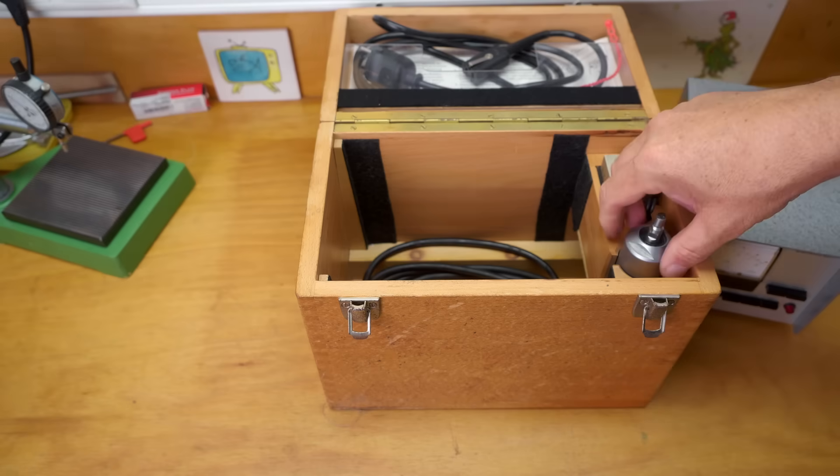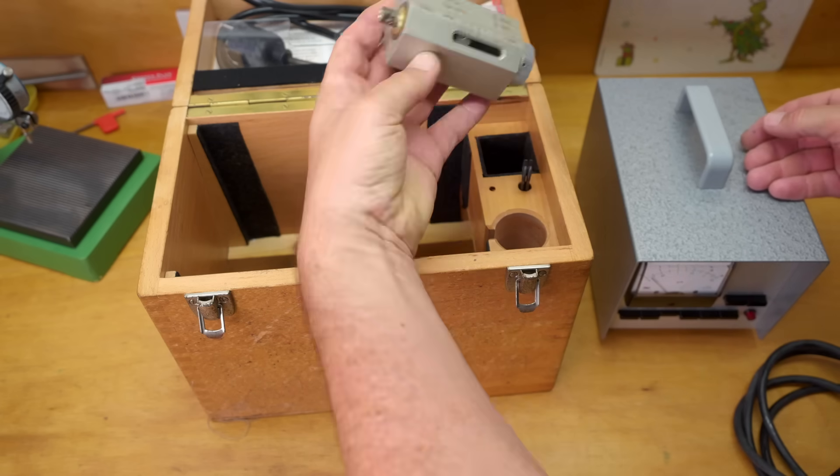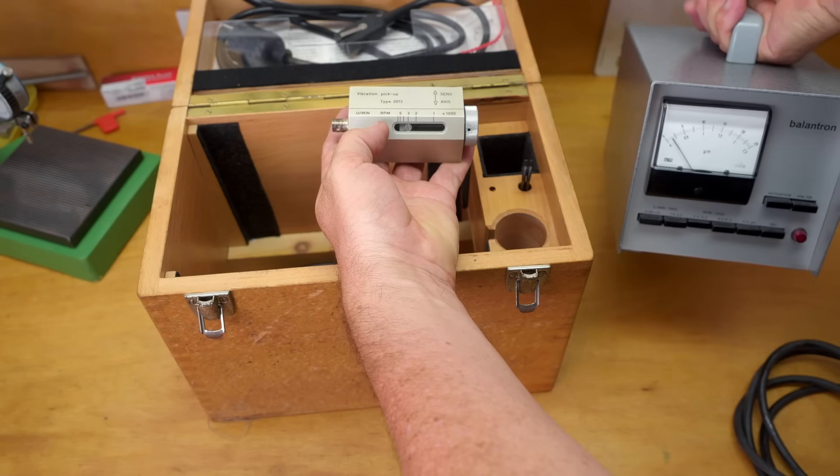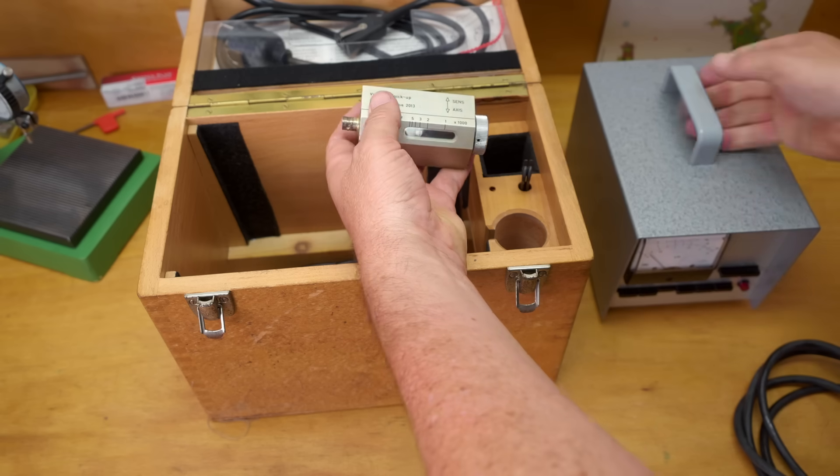The problem with this unit is that this actuator, or as Stefan Gotteswinter put it, handheld highly precise jackhammer, is not working. It's not doing anything. The rest of the system with the accelerometer and the ability to isolate and measure the highest vibration seems to work fine.